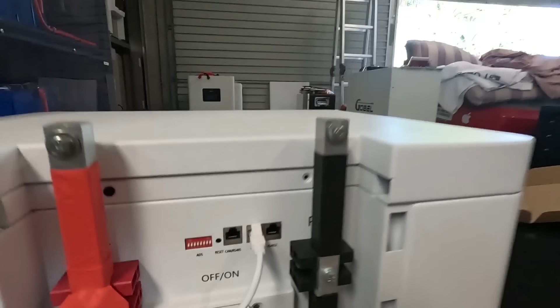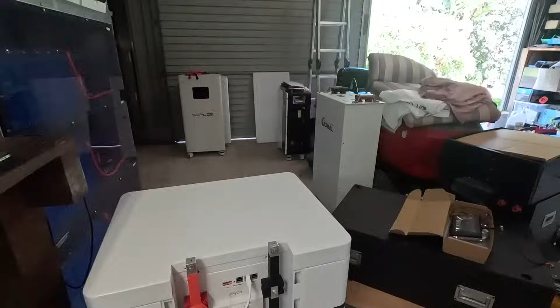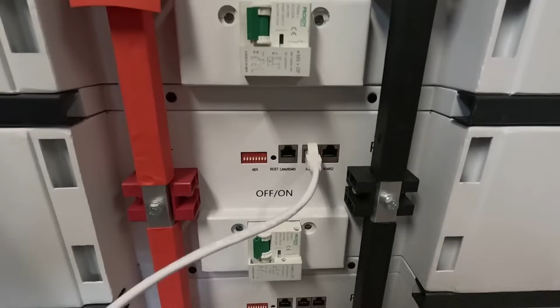There's no life anymore. This means either the BMS is totally dead now because you've chosen the wrong firmware, or it's just asleep. And there it is again. Okay, so this is pretty much the whole flashing process for the version 3 BMS from Seplos, and I'll do exactly the same on the other two BMSs now as well. So in order, I have to disconnect this cable here and plug it to port number 1 down here, then turn this one on, start the flashing process, and do the same with battery number 3.